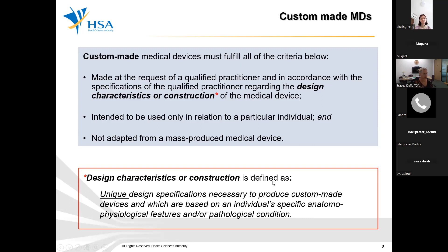An example of a custom-made medical device will be an acetabular cup implant requested by orthopedists in addition to a DICOM compliant scan image. The orthopedist actually sends specific requirements for bridging the areas of the acetabular bone loss in acetabulum reconstruction to a 3D printing implant manufacturer. This will include the thickness, the trajectory of the cup mounting flange, and the number, type, and positions of the fixation screws. So all these requirements are outside of the manufacturer's validated parameters for the specified design envelope, and hence, it will actually be a custom-made medical device.